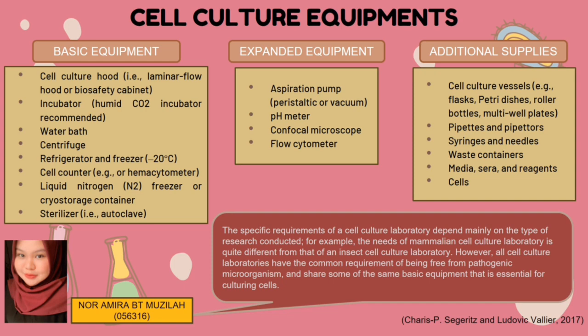Next, cell culture hood. The Class 1 cell culture hood gives significant levels of protection to laboratory personnel and to the environment, but they do not provide cultures protection from contamination. Class 2 cell culture hood designed for work involving BSL 1, 2, and 3 materials and also provide an aseptic environment necessary for cell culture experiment. Class 3 cell culture hood are gas tight and they provide the highest attainable level of protection to personnel and the environment. A Class 3 biosafety cabinet is required for work involving human pathogens and other BSL4 materials. And lastly, airflow cell culture hood, which is to protect the working environment from dust and other airborne contaminants by maintaining a constant unidirectional flow of HEPA filter air over the work area.